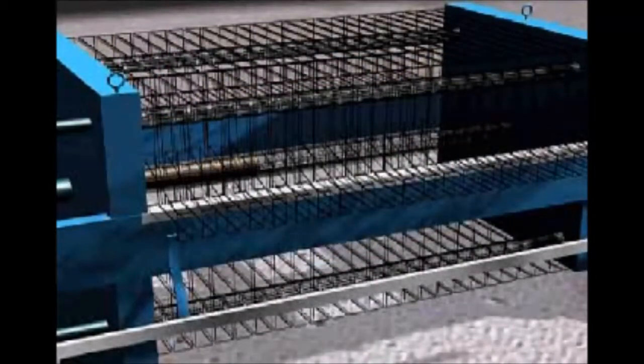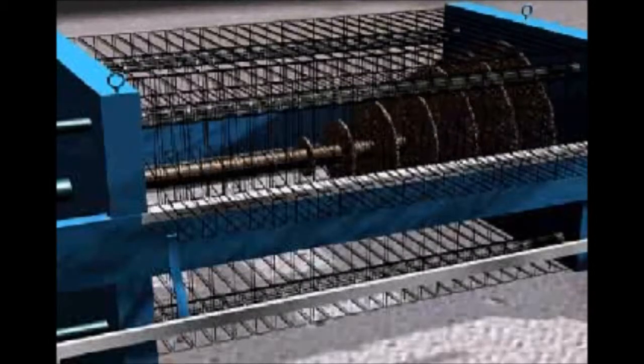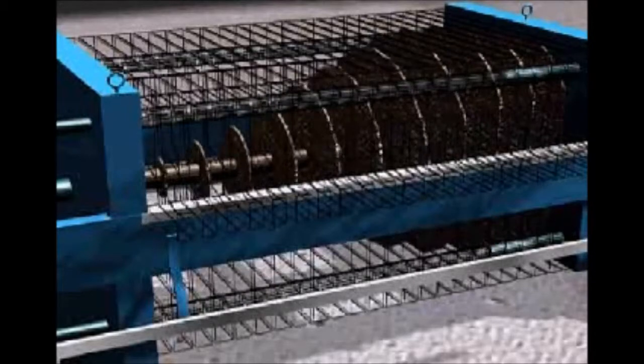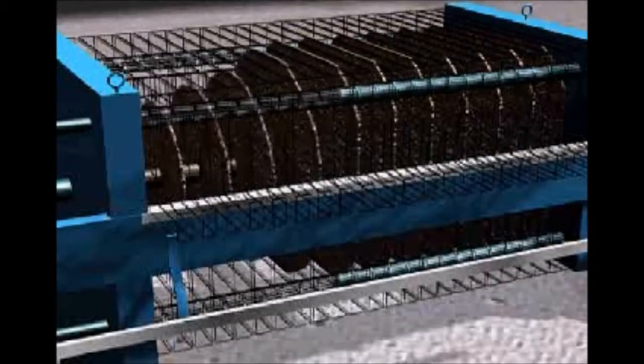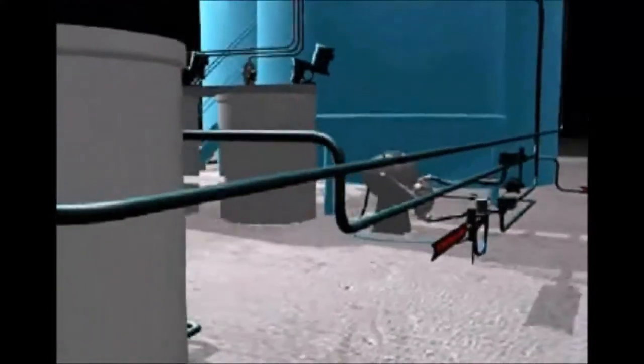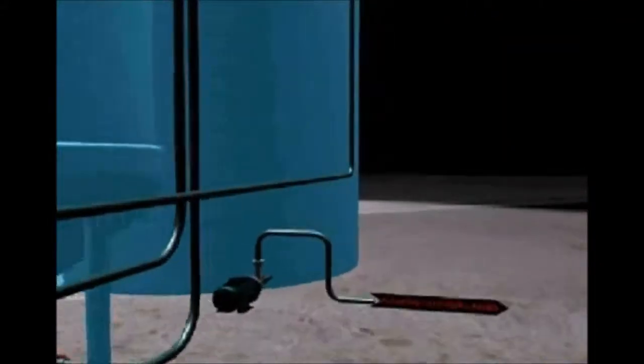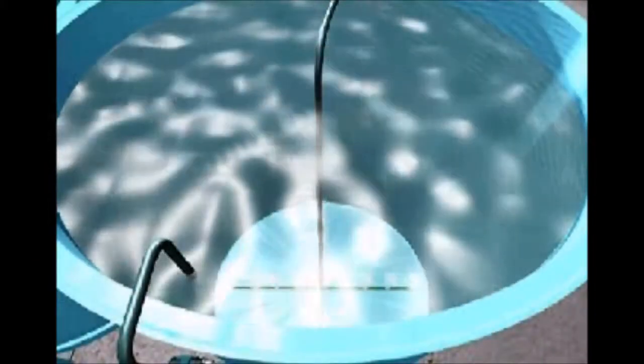The sludge in the treatment tank contains 95 to 99% water, and on being pumped to the filter press, the solids are retained in the chambers of the filter plates, while the filtered water is discharged through the corner discharge ports and collects in an inspection tank. From this inspection, or filtrate tank, the water is transferred to a treated water holding tank that is equipped with air diffusers like the equalization tank. From this tank, the water can be reused in the plant or discharged.